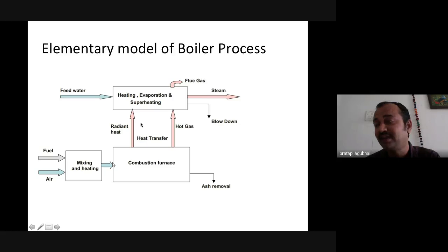Now, after that, the flue gas travels, and through convection, the heat is getting transferred. So in convection, the flue gas heat is applied to the hot water or the steam, which became hot from the radiation energy inside the furnace, and then again it becomes hot. It is catching the heat, and more steam will be available with the rated pressure.